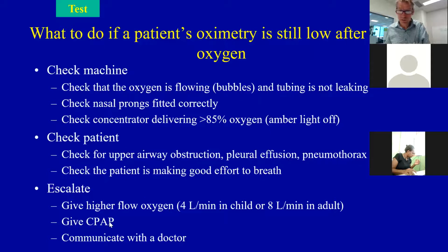Now, the question often arises as to what to do if the patient's oximetry is still low after giving oxygen. And it's a good reading, but the oximetry is still low. The patient's still hypoxic. Well, the first thing to do is check the machine. And so you can check that the oxygen is flowing properly, and I'll show you how to do that at some stage, and that there's no leaking from the tubing. You can check the nasal prongs are fitted correctly and they're not sort of up above the nostrils. You can check that the concentrator is delivering more than 85% oxygen, and I'll show you how to do that when I turn on the concentrator behind me.